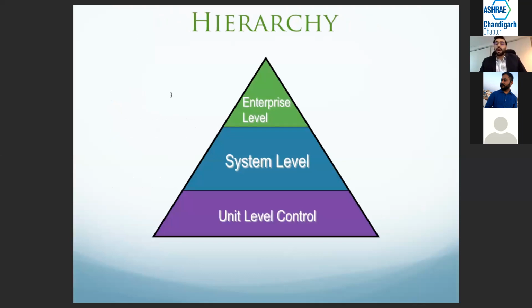From a hierarchy standpoint, we have three different levels. First, the unit level controls. Think about it this way: any piece of equipment that has its own controller has a unitary controller. A chiller is going to have a controller, that's a unit level control. A boiler is going to have a controller, that's a unit level control. VAVs, fan coils, air handlers, you name it, every piece of equipment has its own controller, that's a unitary controller.